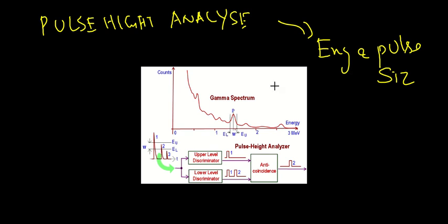It is used to generate a detailed spectrum and thus to resolve a complex mixture of X-rays and gamma rays. A single channel pulse height analyzer is basically a gate, typically some 0.1 volt wide, which only accepts a pulse between an upper threshold level and a lower threshold level. You can think of it as a band pass filter.